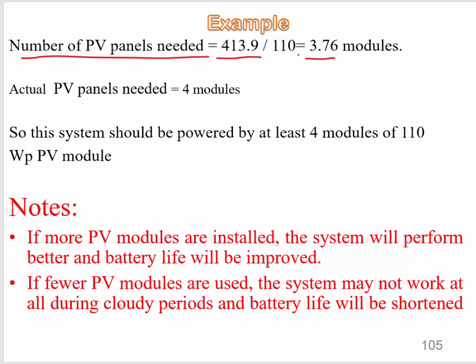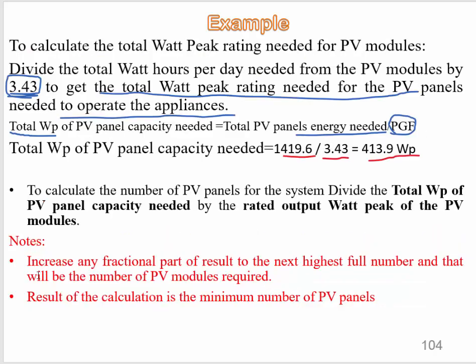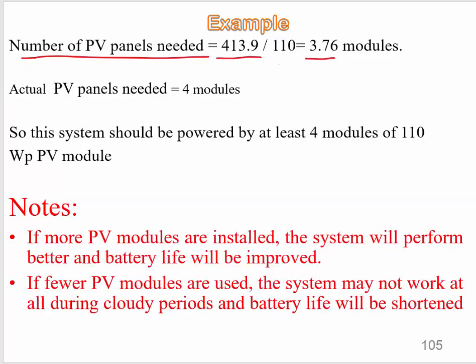The result is 3.76. According to note two, the result of the calculation is the minimum number of PV panels, so 3.76 means we need four modules. This system should be powered by at least four modules of 110-watt peak PV panels.